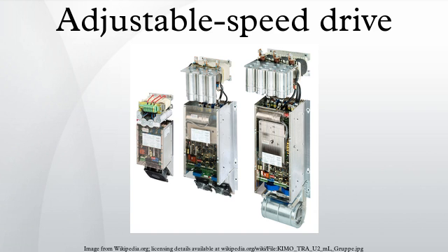Cycling the pumps on and off results in frequent high surges of electric current to start the motors, that results in electromagnetic and thermal stresses in the motors and power control equipment. The pumps and pipes are subjected to mechanical and hydraulic stresses, and the sewage treatment process is forced to accommodate surges in the flow of sewage through the process. When adjustable speed drives are used, the pumps operate continuously at a speed that increases as the wet well level increases. This matches the outflow to the average inflow and provides a much smoother operation of the process.